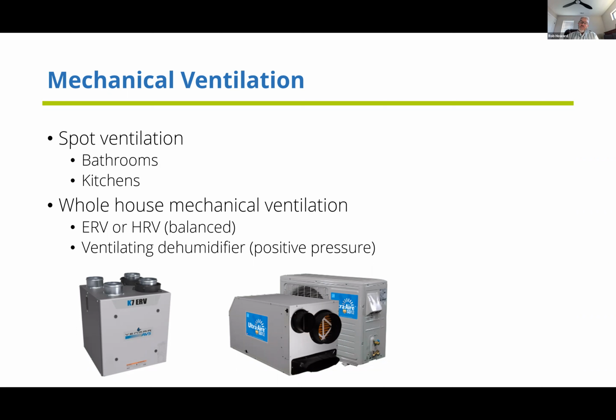Another strategy we tested on a few houses was the ventilating dehumidifier option. The one pictured here is a split system dehumidifier, called the SD12 — I don't know that the manufacturer even makes these anymore. The outdoor unit looks a lot like a mini split heat pump. The beauty of that system is your compressor is outdoors, so you're moving the noise and vibration outside, and you're also dumping the waste heat outdoors. As a byproduct, you end up with about a third of a ton of cooling off that unit, so I thought it was a pretty cool device. Unfortunately it was also very big and quite expensive.